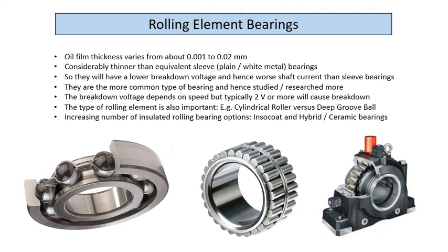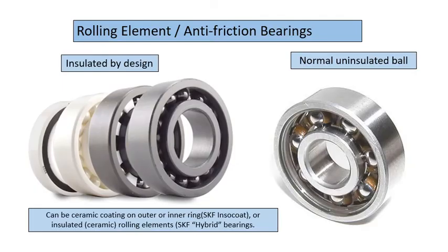Then there's an increasing number of insulated rolling bearings options. I'll show that later, both InsoCoat and hybrid ceramic bearings. InsoCoat is SKF's trade name for a rolling bearing where you insulate either the outer ring or the inner ring with a ceramic coating, or both, I think. I don't know if they do both. There we go. There's your insulating coating. So it can be on the inner or outer ring, and then that's a normal uninsulated. So you see it's steel balls.